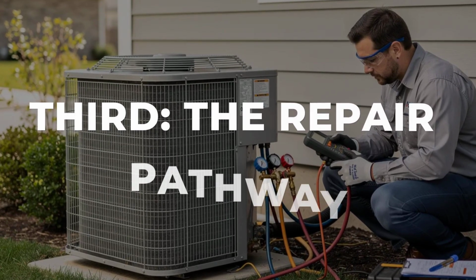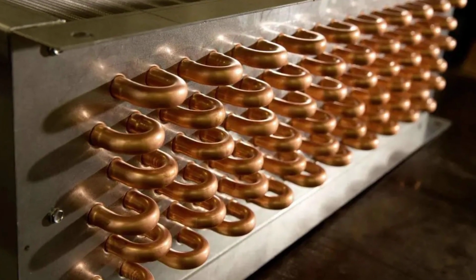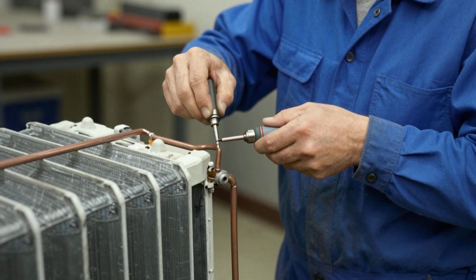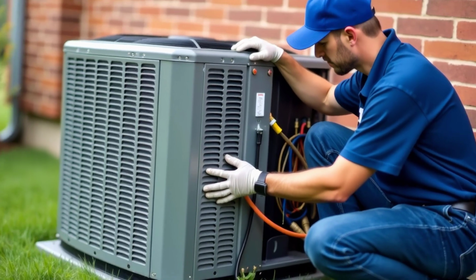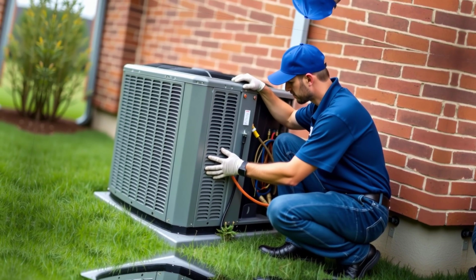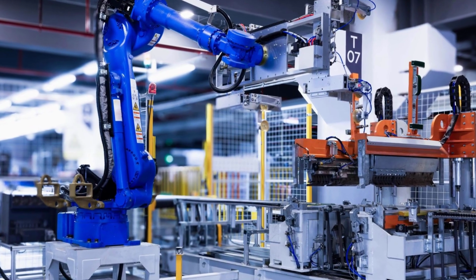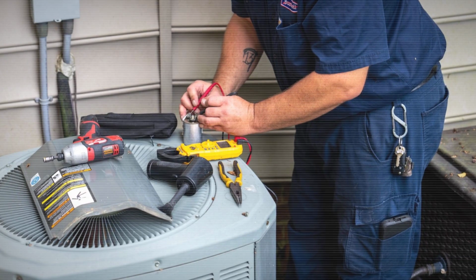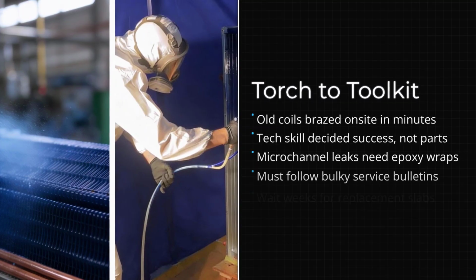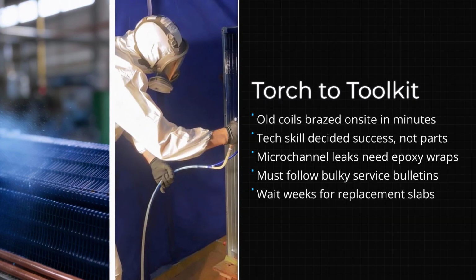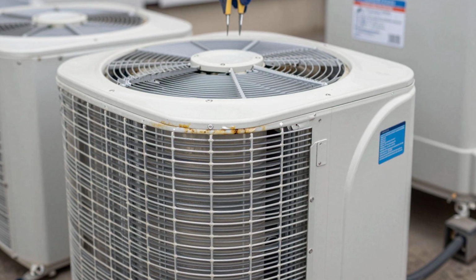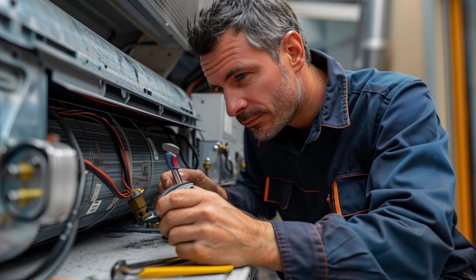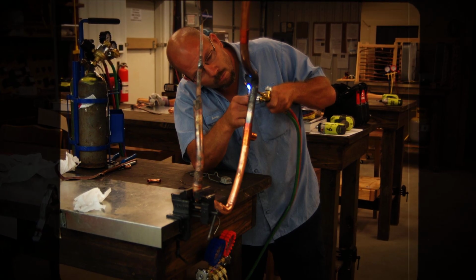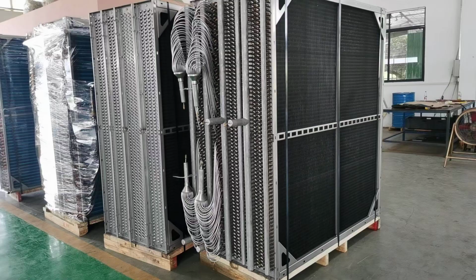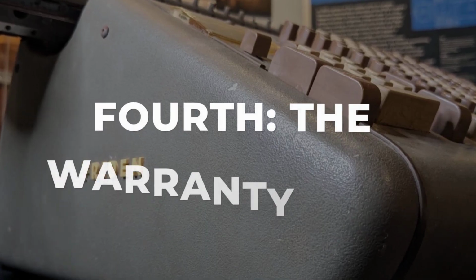Third, the repair pathway. The old coil was a broadly serviceable component. A technician with a torch, some brazing rod, and 20 years of muscle memory could fix most leaks on site, same day. The new microchannel coil is a module. Trane's service bulletin describes a temporary field repair kit involving epoxy, an aluminum wrapper, and a controlled heat cure for leaks in the flat tube area only. If the damage is anywhere else, you are ordering a replacement slab. That is not a repair culture. That is a parts cannon culture designed to move units. Fourth, the warranty math.